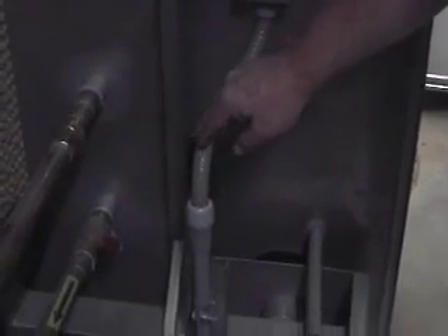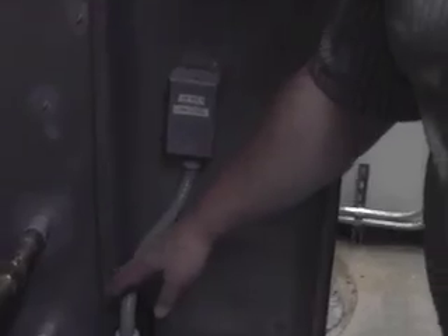So real quick, I just want to point out, this right here is a low level sensor. This is designed to lock out the evaporative media pump from running if there's no water in the sump. The way that we enable the system to run for 15 or 20 minutes, but if for some reason the makeup valve didn't open and there's no water, we don't want to burn the pump up. So this sensor right here actually disables the pump from running.